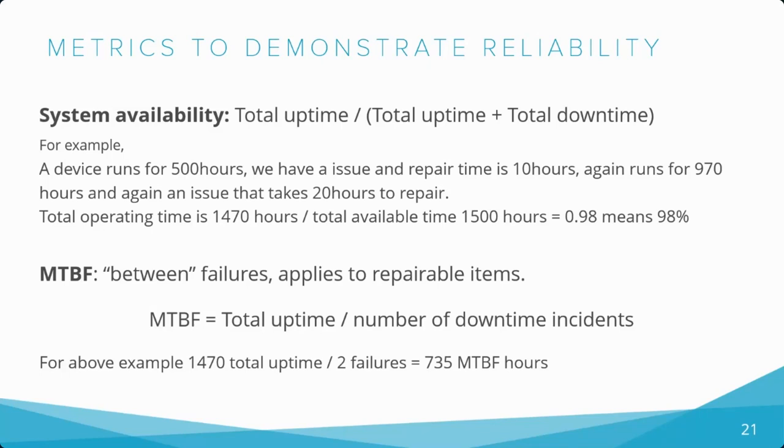MTBF, mean time between failure. As the name says, it's the mean exposure time between consecutive failures of the component, which applies to repairable items. The MTBF for the device discussed above would be the total uptime of 1470 hours divided by two incidents, making the MTBF 735 hours.